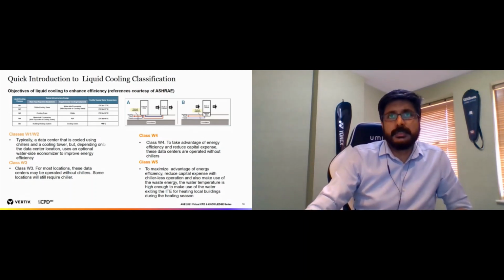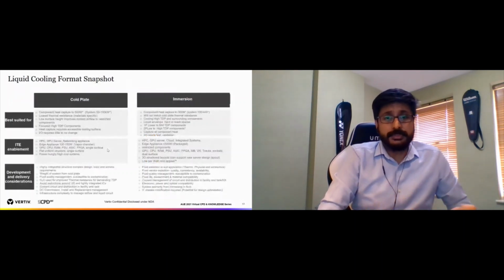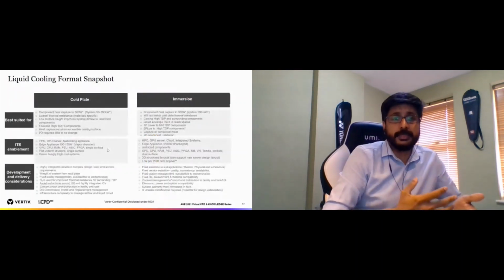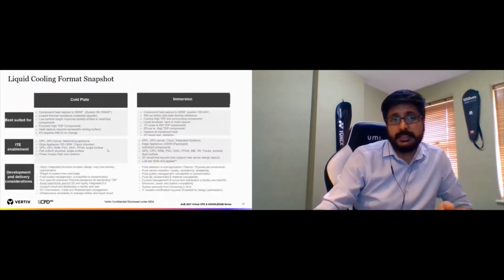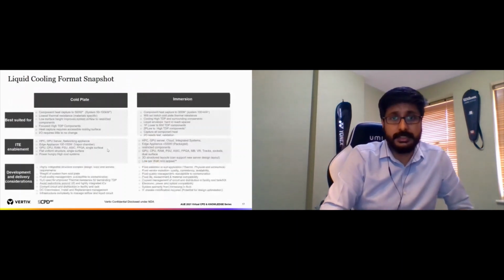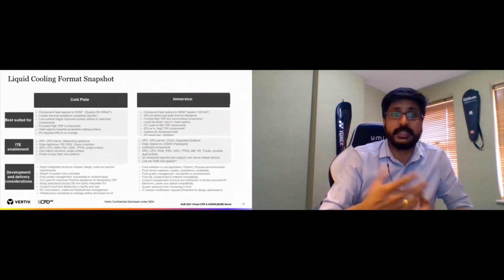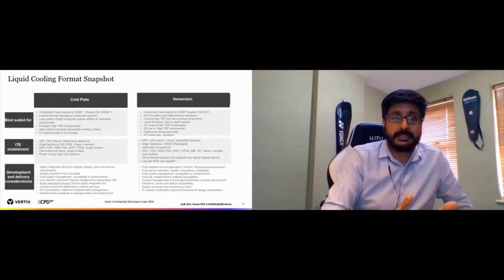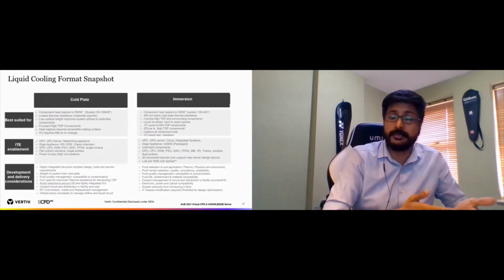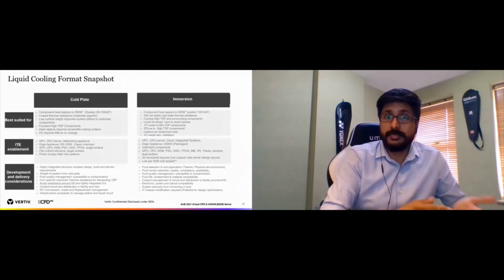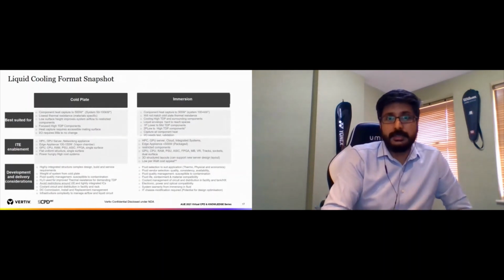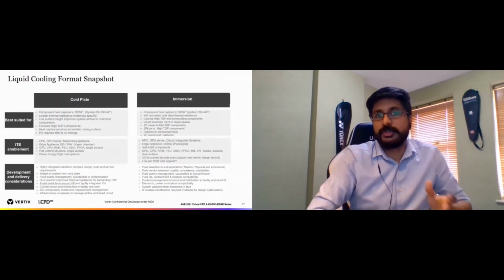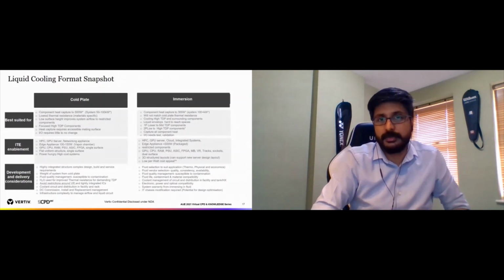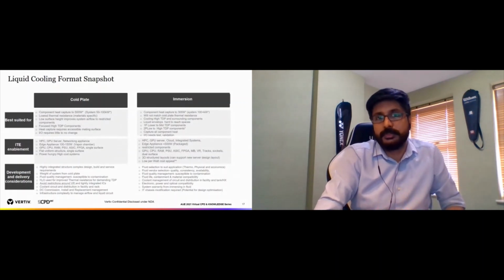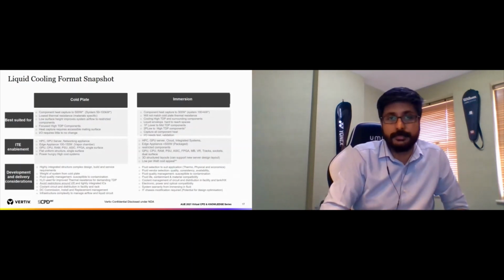And finally, just a comparison between cold plates and immersion cooling, to give you a rough idea. Usually cold plate cooling is best suited when the system heat is around 100 kilowatts. Immersion is used where there's more than 100 kilowatts, so it gives you more and more heat rejection. But the thermal resistance on the immersion side is quite a bit higher compared to cold plate, because in the cold plate we use water or an ethylene glycol solution, but in immersion it has to be a dielectric fluid. Because the application can reach more of the components, it can be used to cool higher TDP components as well.